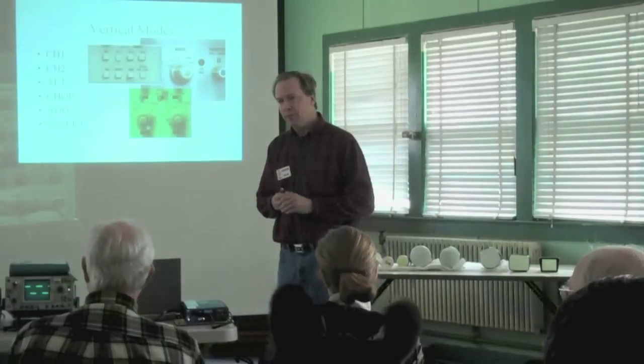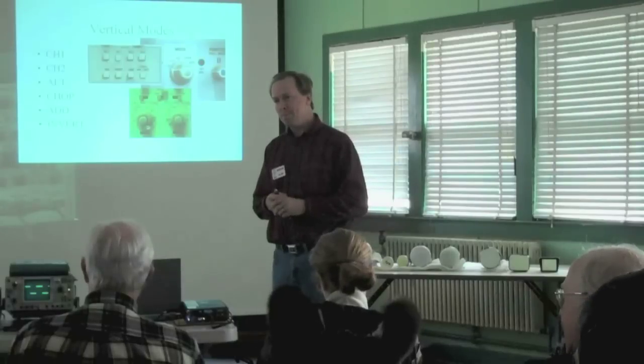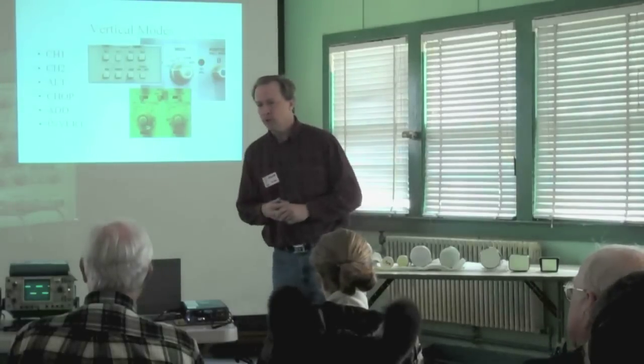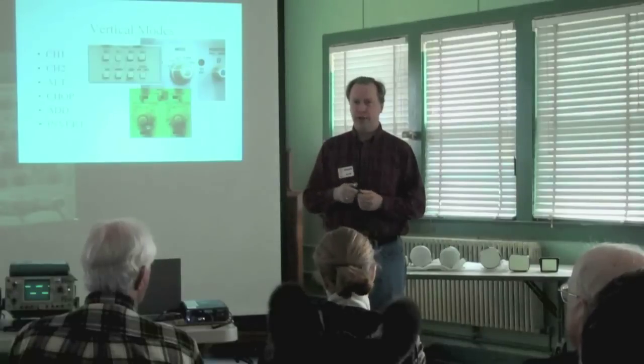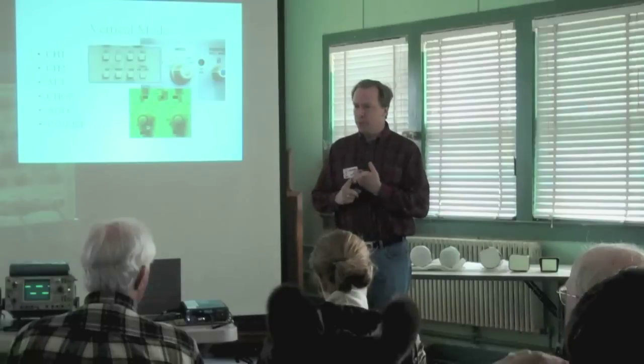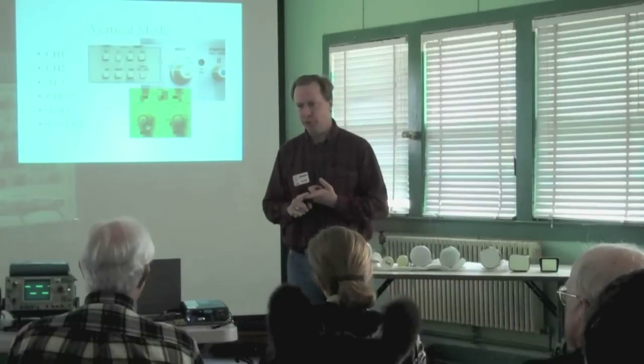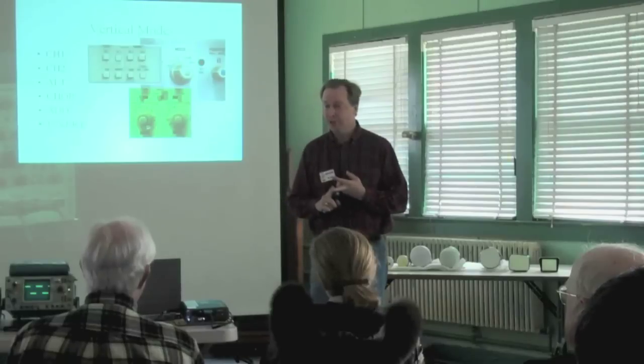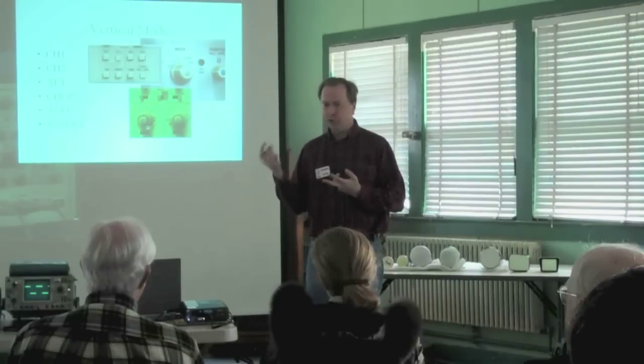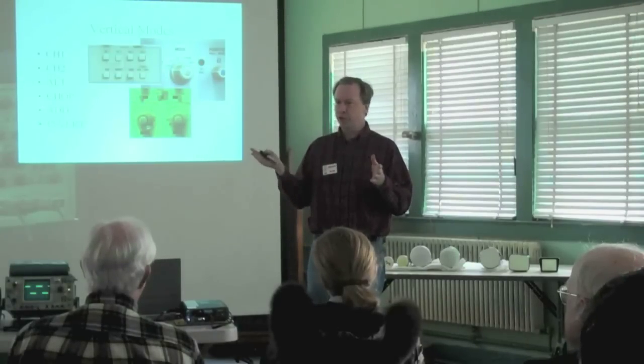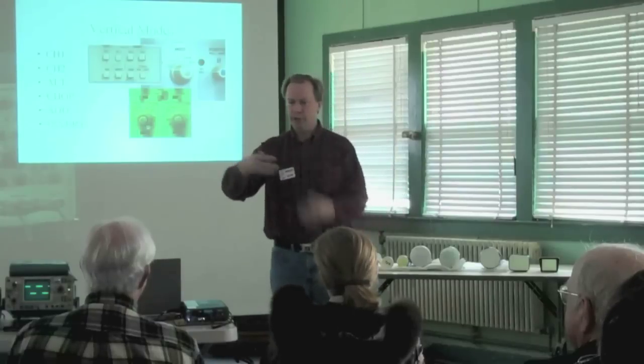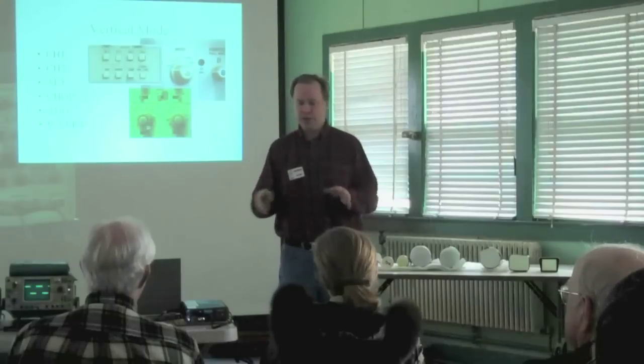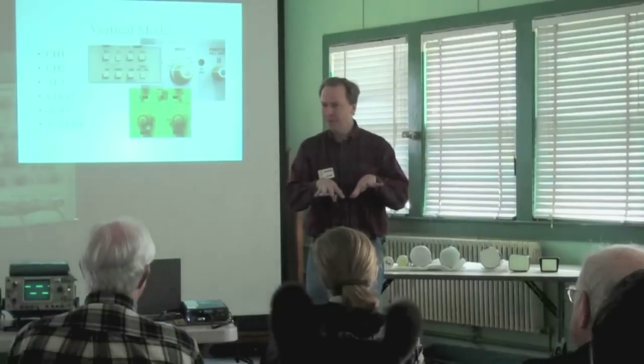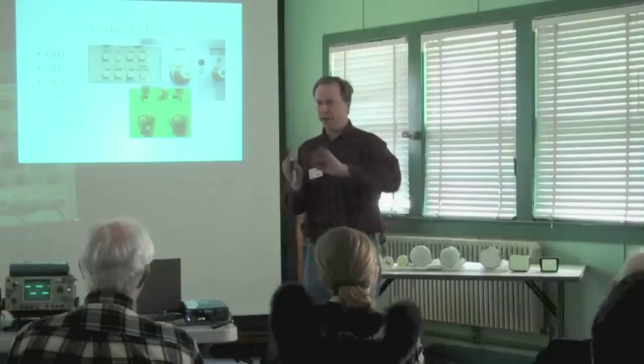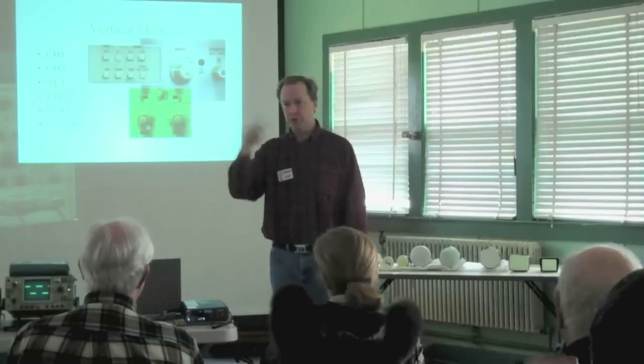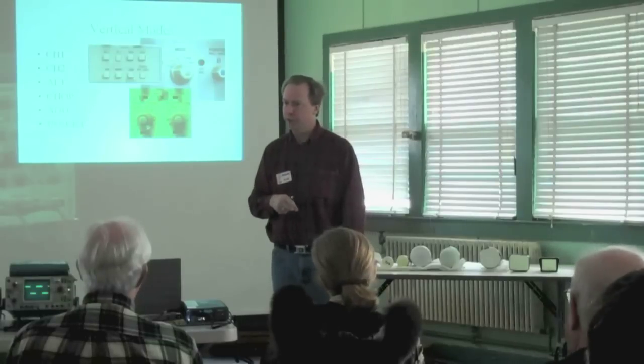The question is, are all the scopes now single beam or are they dual beam? The reality is there aren't a lot of people making CRT-based oscilloscopes anymore. Most scopes made today are digitizing scopes, where the signal comes in, gets digitized by an analog to digital converter, and those samples get displayed on a computer-like display. So we're sampling all these signals at the same time. If it's a 4-channel scope, it's 4 channels, and the display just shows the result of those. There isn't really a sweep or a beam associated with each one anymore.